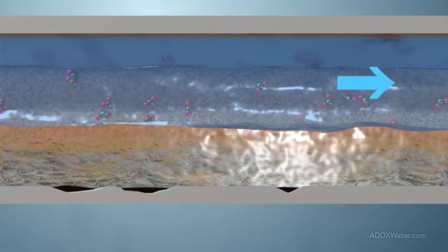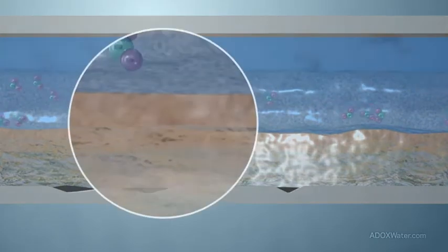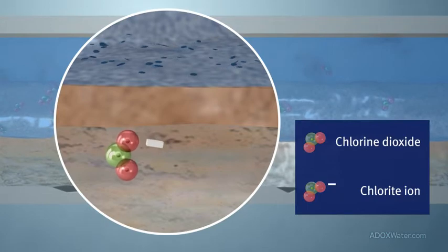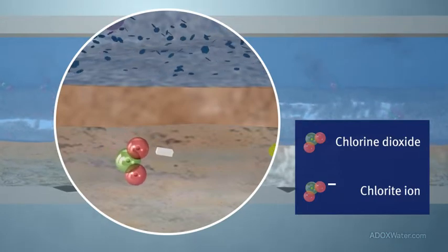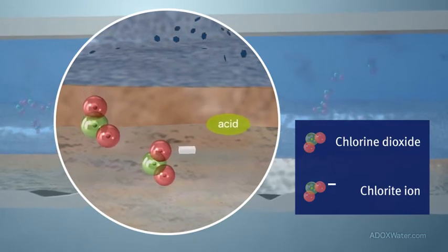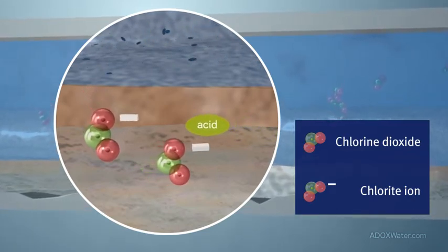In addition, as chlorine dioxide reacts as a biocide, chlorite ion is formed as a ClO2 disinfection byproduct. When chlorite ion encounters acids, such as those produced by SRBs and APBs, chlorine dioxide is reformed in situ.